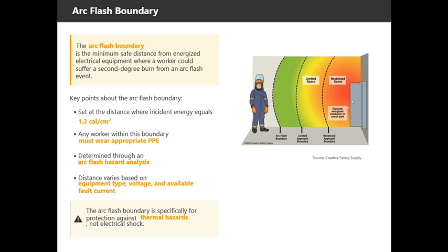Finally, the distance varies significantly based on equipment type, voltage level, and available fault current. It's crucial to understand that the arc flash boundary is specifically for protection against thermal hazards from arc flash, not electrical shock. This is a common misconception. The arc flash boundary and shock protection boundaries serve different purposes and are calculated differently. The arc flash boundary isn't a fixed distance, it's specific to each piece of equipment and must be calculated based on the electrical characteristics of that equipment and the system it's connected to.